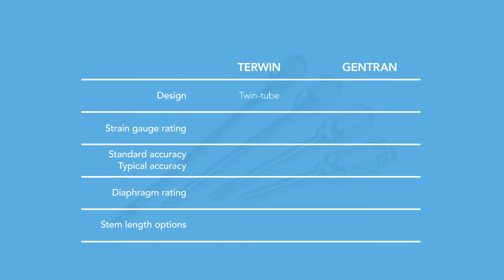A proprietary twin-tube system overcomes problems of temperature drift associated with old force rod type transducers like Gentran. Terwin's strain gauge assembly is rated to 200 degrees C. Most competitive transducers have a head that is suitable for only 121 degrees Celsius, requiring a length of flex armor at an additional cost.